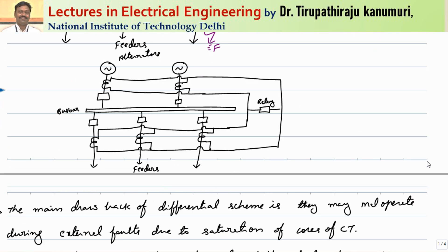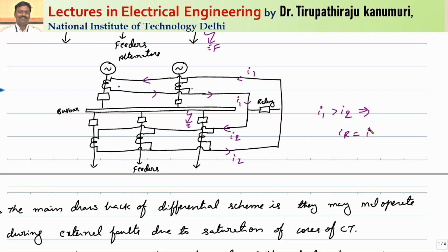Now let us take the case of internal faults. If some fault happens on the busbar, the current supplied will be greater than the current taken out from the outgoing lines. Analyzing the currents: the net sum of currents from the outgoing CTs I represent as I2, and the current supplied from the source I represent as I1. Whenever the fault happens, the value of I1 is greater than I2, so the current passing through your relay will be I1 minus I2, which is non-zero, and your relay will operate.